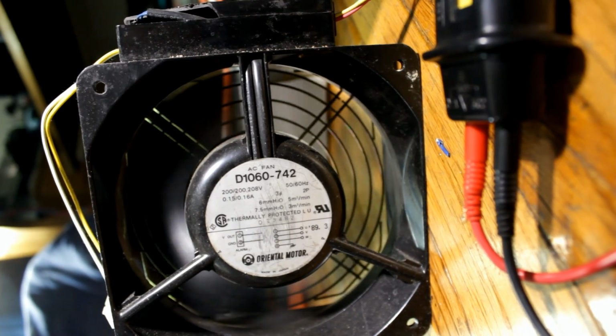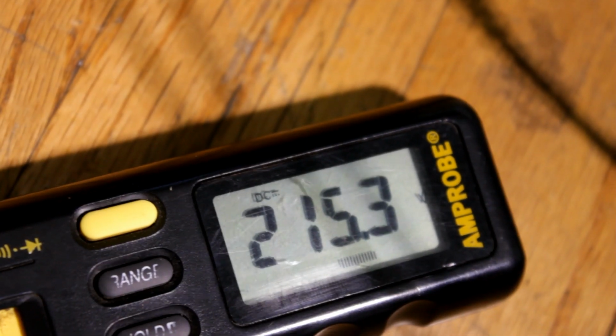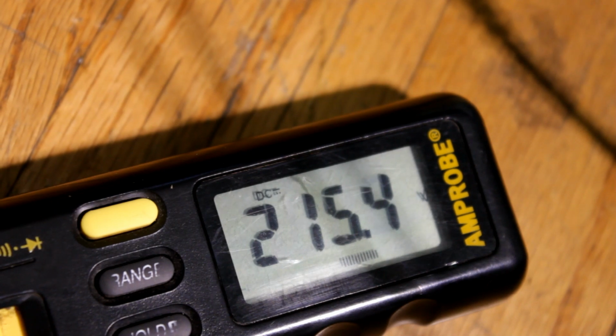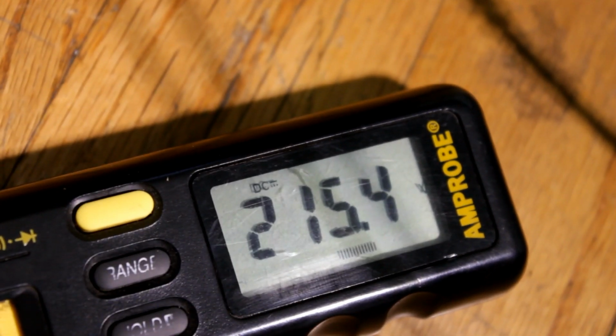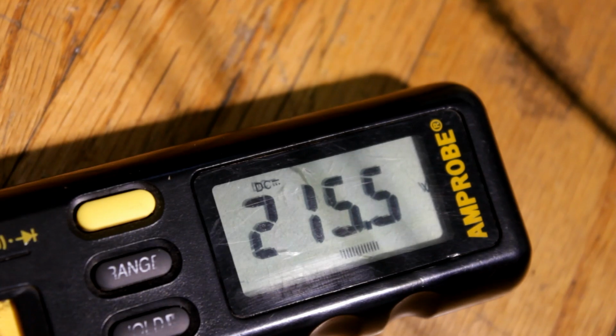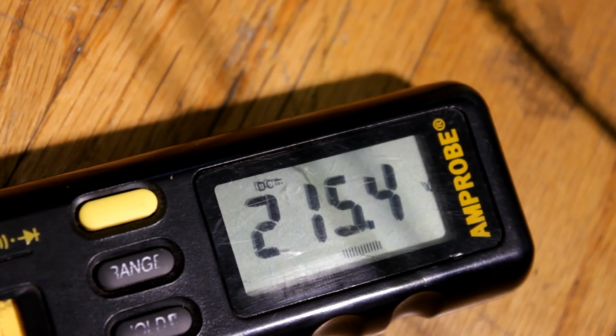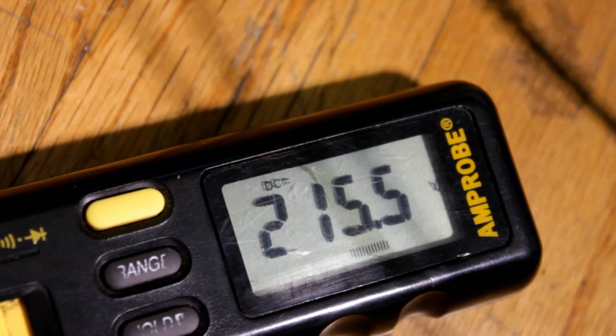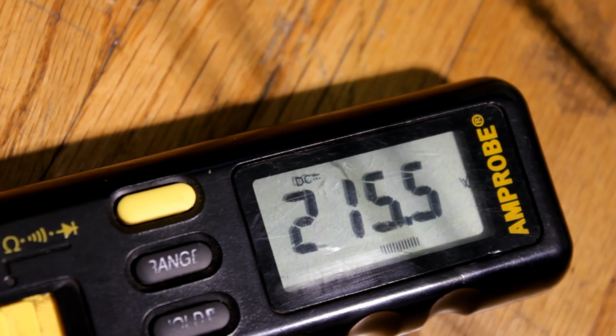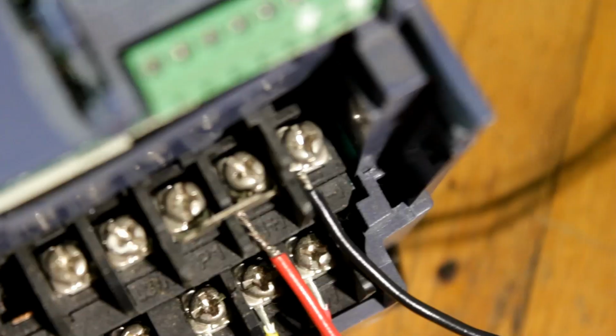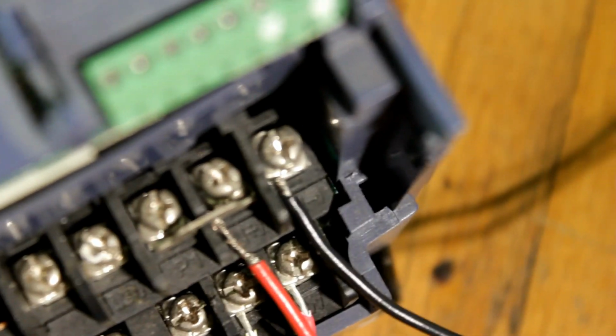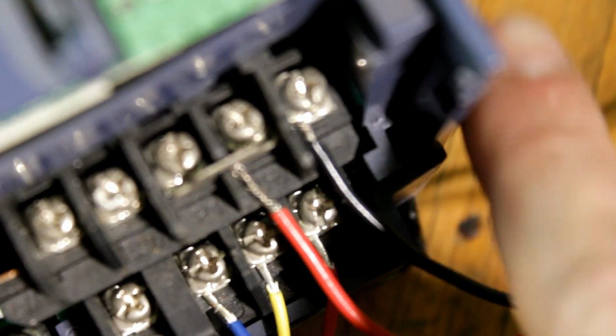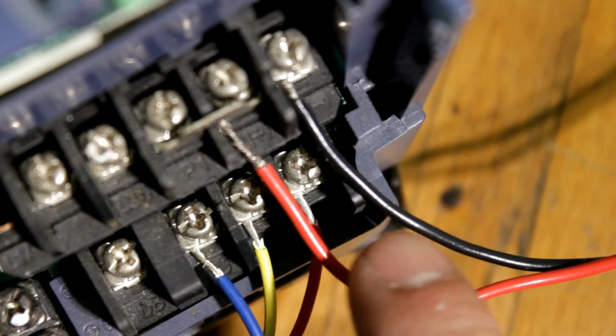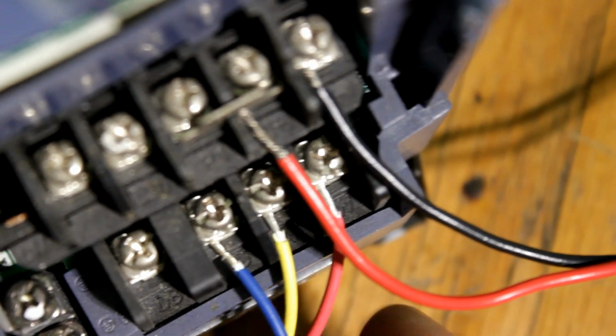But anyways, it seems to run reasonably well at 215 volts DC. But in reality, for a 240 volt drive, you probably want a bus voltage of around 340 volts. For a 480 volt drive, you're probably going to want a bus voltage of double that. So keep that in mind. And let's get a nice close-up real quick. That's the negative there, that's the bus positive there, and then U, V, and W out to the fan.